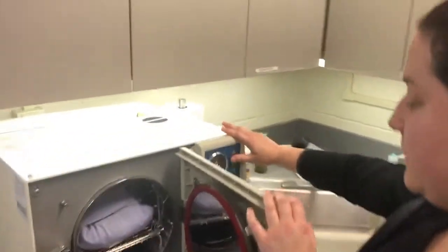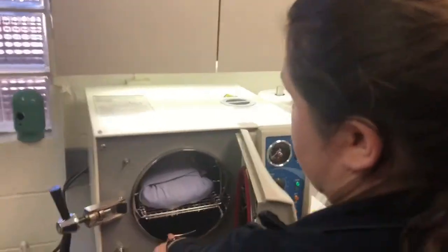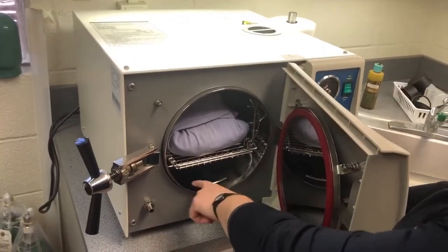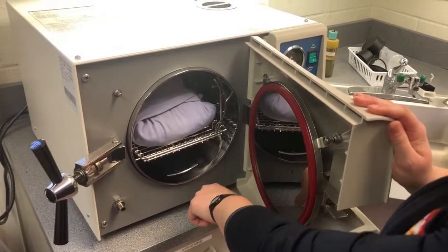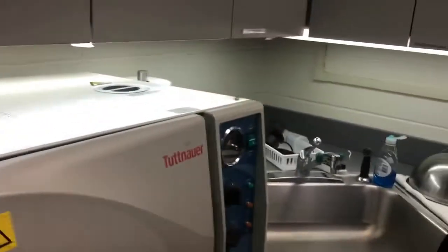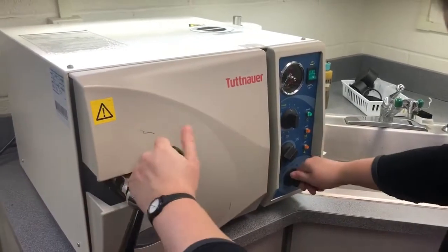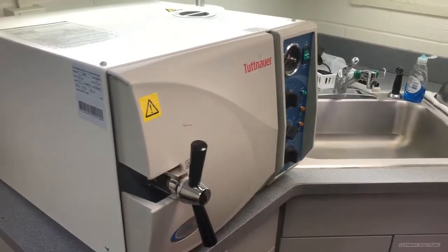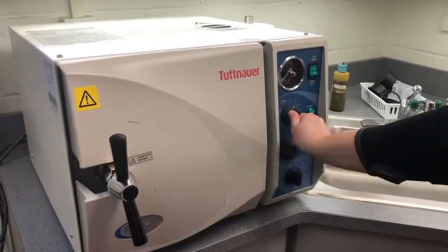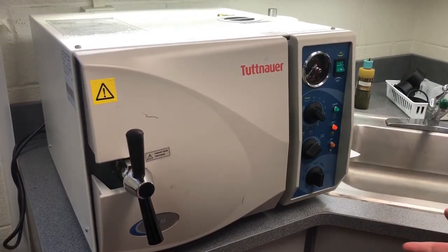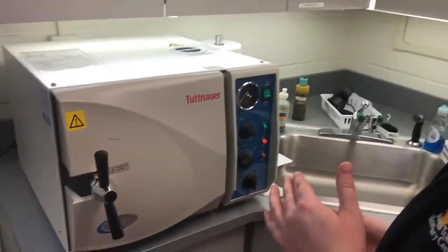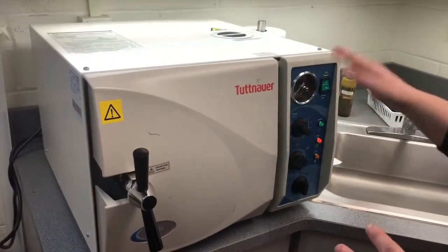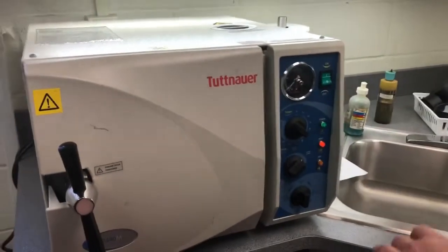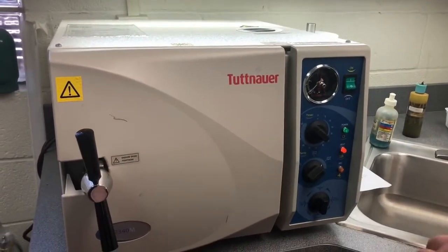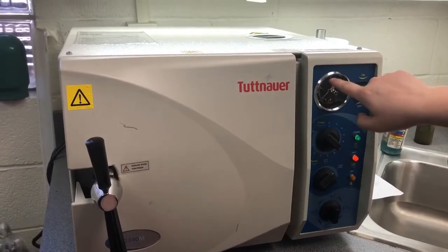And then turn the autoclave on, and ours fills with distilled water here at the bottom. So once it gets to this little ridge here, then it's ready to sterilize. So I'm gonna close it, and then switch this to sterilize. And you want it to be really tight, but not so tight that you can't open it when it's done. And we generally set the timer for about 25 minutes to give it some time to build up pressure, because you want it to be in the ideal pressure between 15 and about 27 psi for 15 minutes. And then you also want the temperature to be around 250 to 270, so that's all on this dial here.